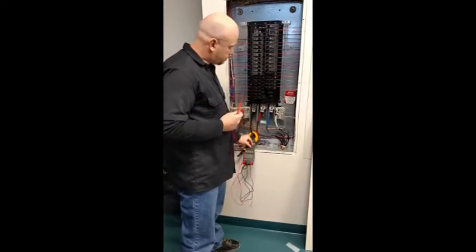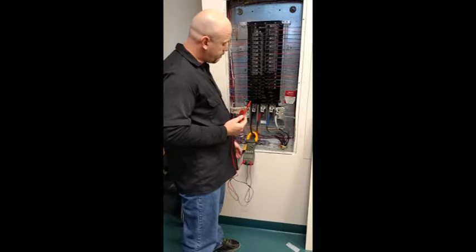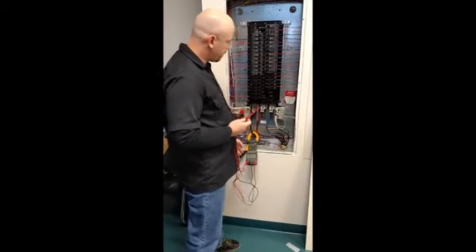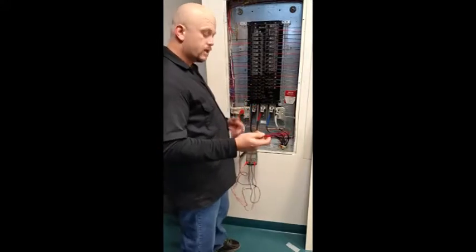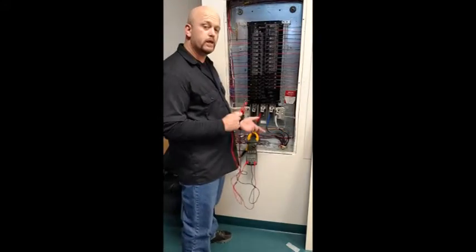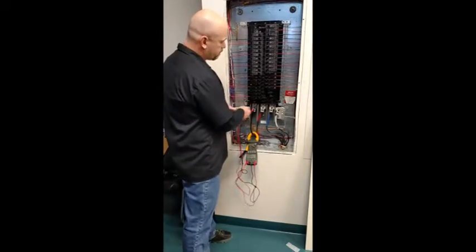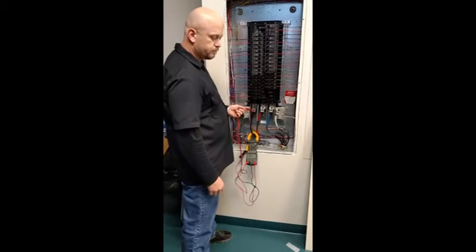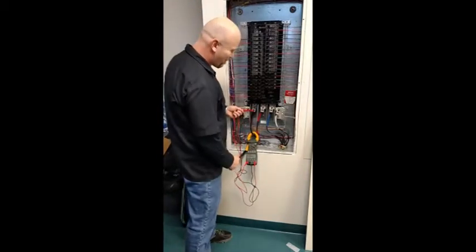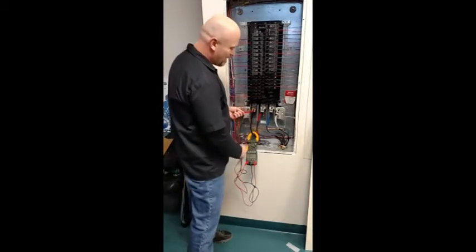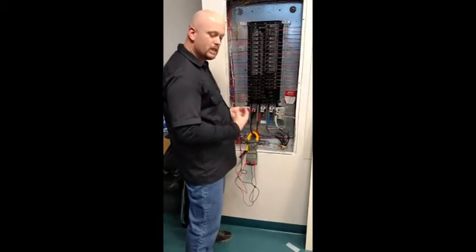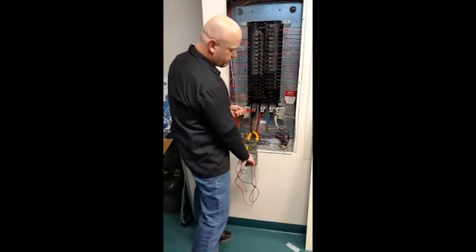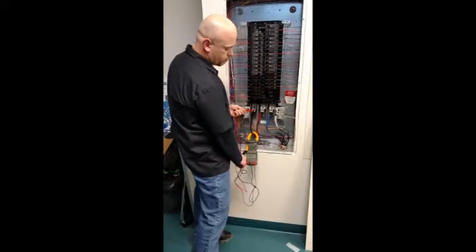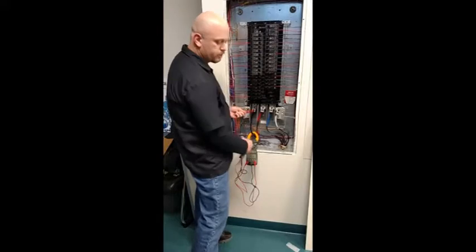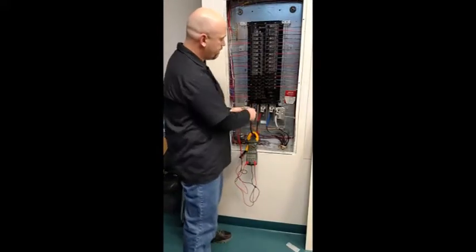The selector is turned 2 clicks to the left to the single phase area. Even though we're doing three-phase, in a Y configuration we want to go into single phase, and we will probe this lug with the probe and get the same kind of ratings that you would get in a single phase situation. You will get voltage, amperage, bottom left and then bottom right, and then the power factor of all three combined phases on the system.